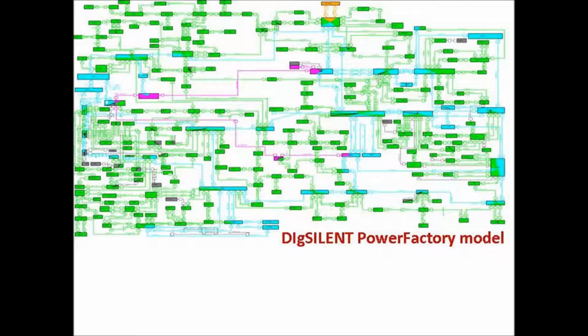Obviously, we've got the background recordings from the previous slide. We lashed that into the model, and then we would look to make sure that we can recreate that. So the model should spit out what's been recorded in reality. Once we've got the two of them lined up, we can then add in new infrastructure, whether it be new cable, or new capacitors, or new turbines, or whatever it happens to be, the internal network of your wind farm. We can put in lumped or distributed models, geometric shapes of the cables, all of that sort of stuff can be all put in. So you've got a very, very accurate model.